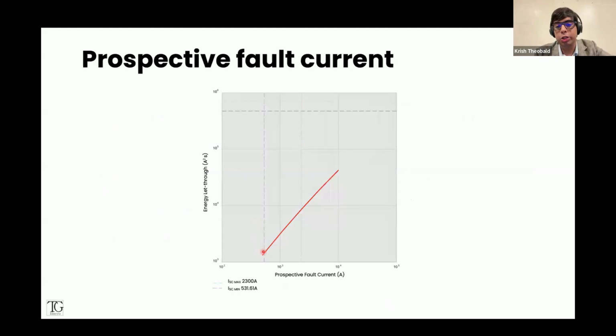So generally, this is done in a graph. The manufacturer gives you a line saying our device will allow a certain amount of let-through energy for a certain amount of fault current, and this is your minimum fault current. So this will be a short circuit current at your extremity. This is your maximum closer to the protected device, and this is the withstand of the cable. So does our device ensure that let-through energy is always less than the cable can withstand? So in this case, yes.